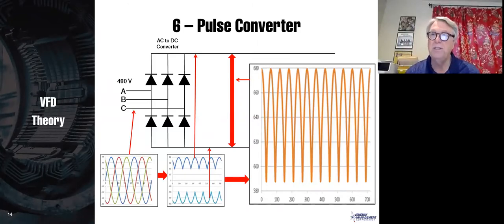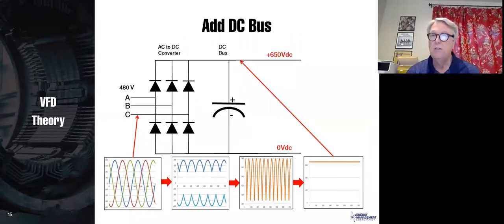The problem is we still have some AC ripple current on there. So how do you get rid of AC ripple current? Well, if it was in a plumbing system, you might add a reservoir. So that's exactly what we do, is add a reservoir. A reservoir in electrical terms, of course, is a capacitor. So we've got these pulses of current coming in, and the pulses of current are really the problem with drives as far as harmonics go, and we will talk about that in a couple more sessions. But when these pulses of current go into the reservoir, it fills up to a level of about 650 volts. Now that will go down a little bit as you load the drive. It can be affected by line reactors and so on, but 650 volts is an approximate value that you would see on the DC bus.